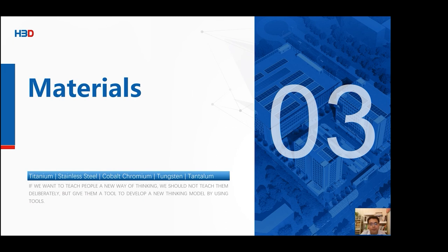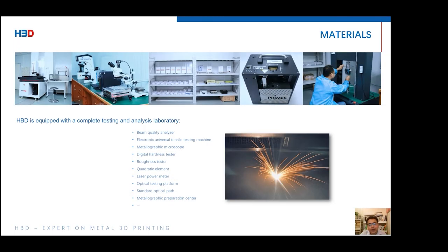I'd like to quote Mr. Yu Jin Ye, the founder of H3D Company: 'Over the years, we have been insisting on all the achievements of metal 3D printing technology in the field of medical devices, and are committed to translating doctors' knowledge into enterprise practice.' The most used materials are titanium alloy, stainless steel, cobalt-chrome alloy, pure tungsten, and tantalum. When 3D printing medical devices we must take into account chemical composition, mechanical properties, physical properties, and microstructure of the printed parts. As a provider of additive manufacturing solutions, we use complete testing equipment including beam quality analyzers, tensile testing machines, and roughness testers.